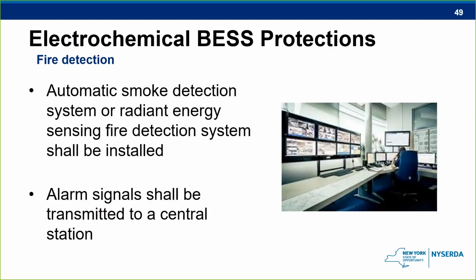When systems are inside a controlled room or enclosure, the smoke alarm is generally the easiest way to sense a fire. When not possible, radiant energy sensing systems can check for excess heat. And if there's a temperature rise, they can send a signal to an alarm panel that will notify the fire department that there's a problem. Central or remote monitoring stations are used to monitor the systems and any alarms. It's important that these are in a safe location, away from any potential hazards, and constantly manned.